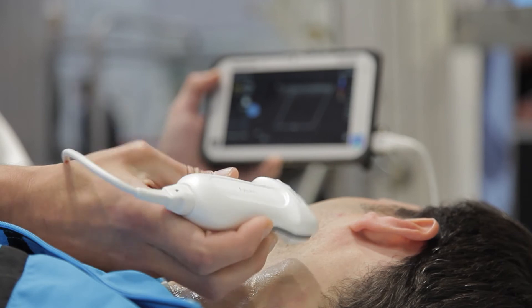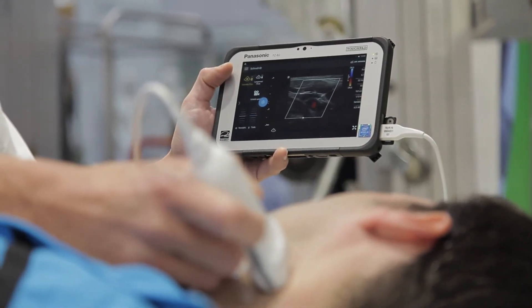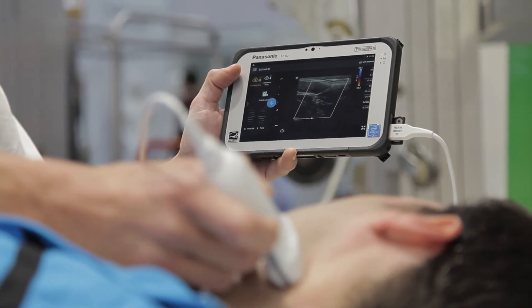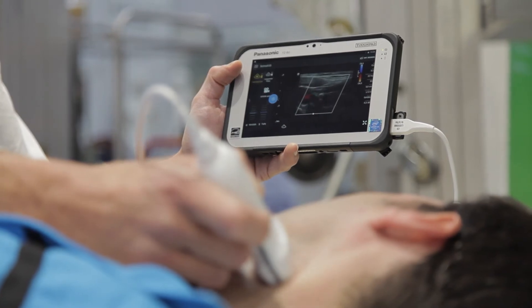Or here, an ultrasound device for ambulance, home visit, or military use. Incorporated into the headpiece itself are the transducer and the complete electronics. It is displayed on the tablet or mobile phone — only one program has to be installed.